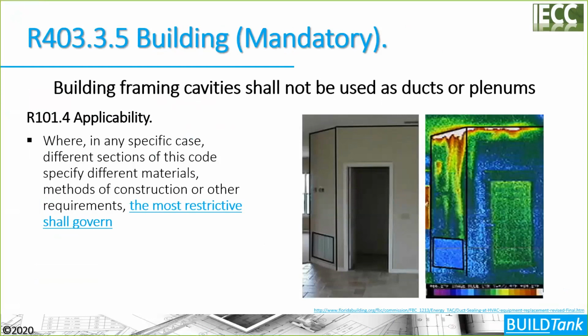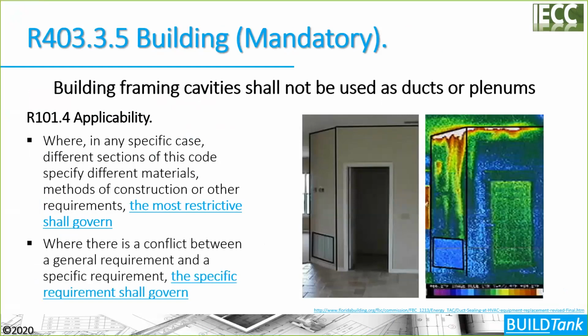Plenum can be defined as a building cavity, but the way that it's used in code is really meaning a ducted building cavity. So some contractors you might come across say, well, I can use a building cavity. Well, the most restrictive should rule. So if you go to this section of the IECC, it's very clear here that you can't use a building cavity as a pressurized duct system.